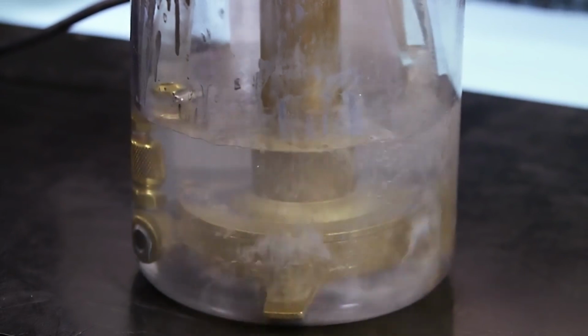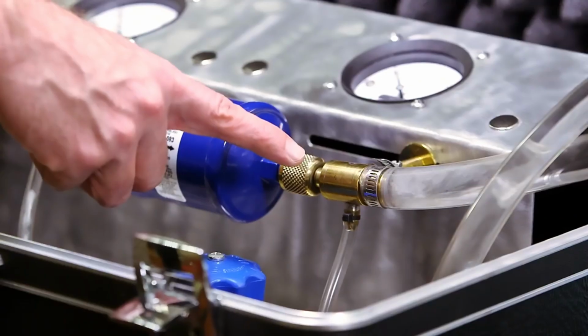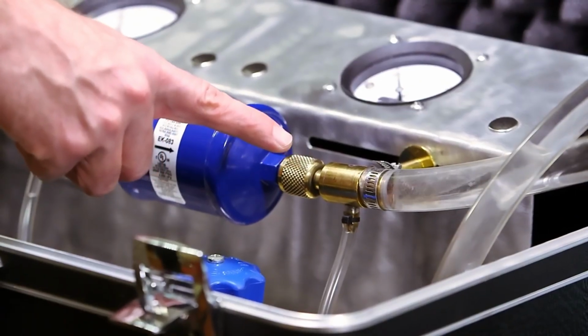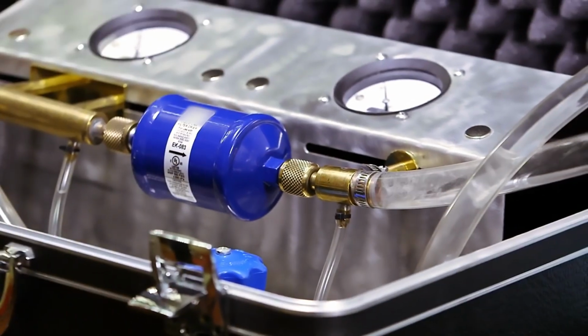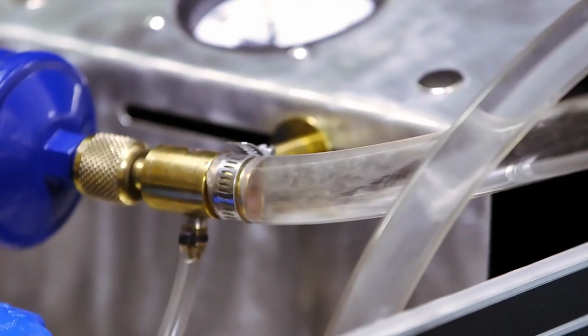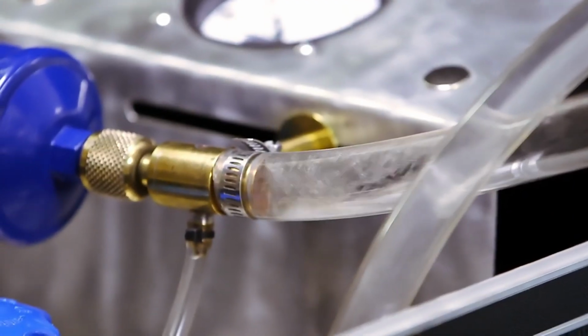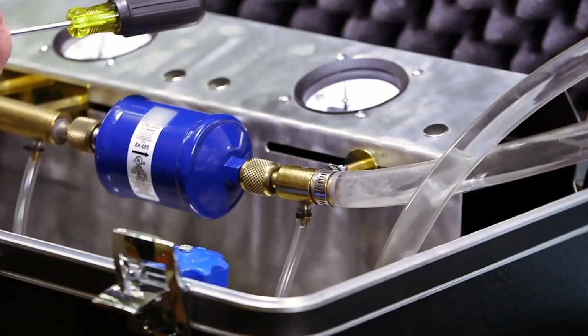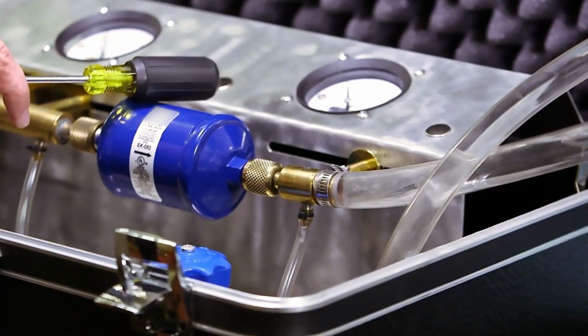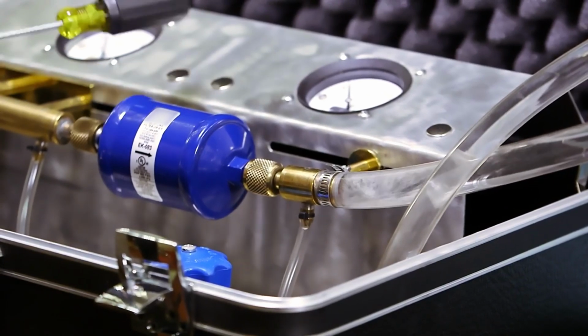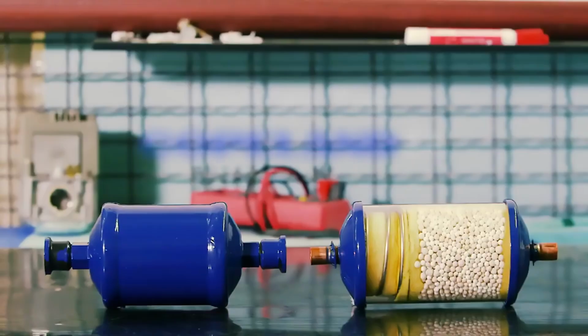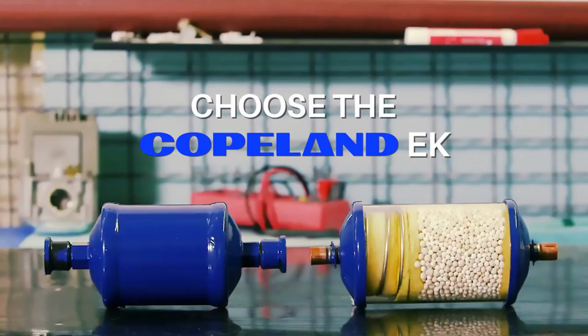When we start and stop the pump to mimic system cycling, the outlet line of the dryer remains clear, demonstrating that the EK filter dryer continues to hold the contaminants. By tapping on the Copeland EK, we simulate system vibration once again. The line remains clear, showing that the filter dryer is retaining the contaminants. For best-in-class 20-micron filtration, choose the Copeland Compacted Bead Liquid Line Filter Dryer.